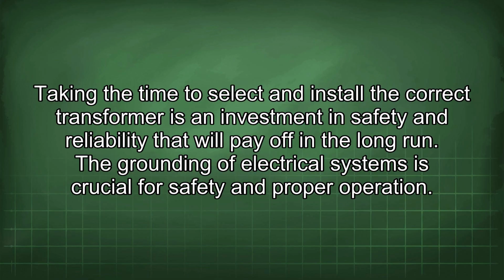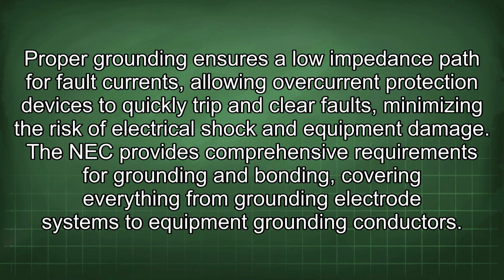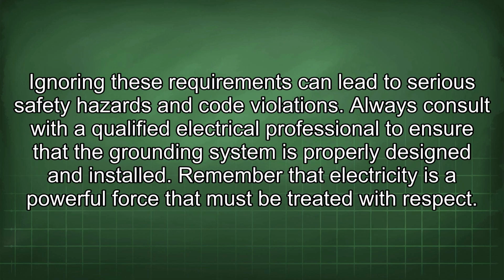The grounding of electrical systems is crucial for safety and proper operation. Proper grounding ensures a low impedance path for fault currents, allowing overcurrent protection devices to quickly trip and clear faults, minimizing the risk of electrical shock and equipment damage. The NEC provides comprehensive requirements for grounding and bonding, covering everything from grounding electrode systems to equipment grounding conductors. Ignoring these requirements can lead to serious safety hazards and code violations. Always consult with a qualified electrical professional to ensure that the grounding system is properly designed and installed.